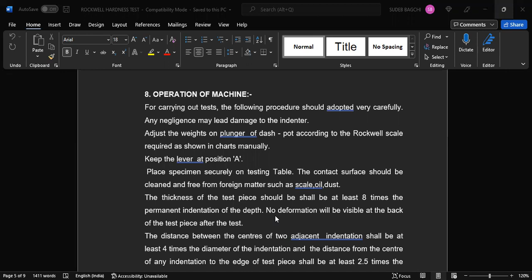Another important thing: the distance between two consecutive indentations should be at least 4 times the diameter of the indentation. The idea is that we can use and reuse the test pieces a number of times, but there should be a proper way of using them, keeping each indent at least 4 times the diameter away from the indent originally made.